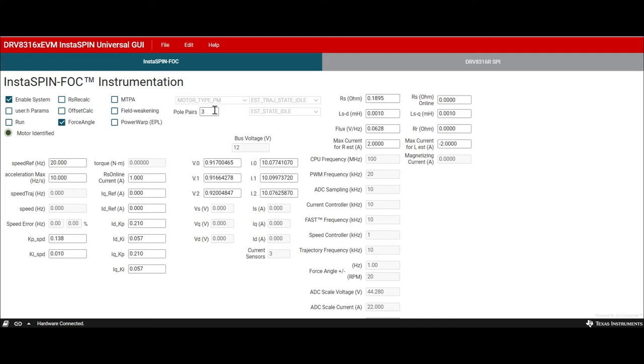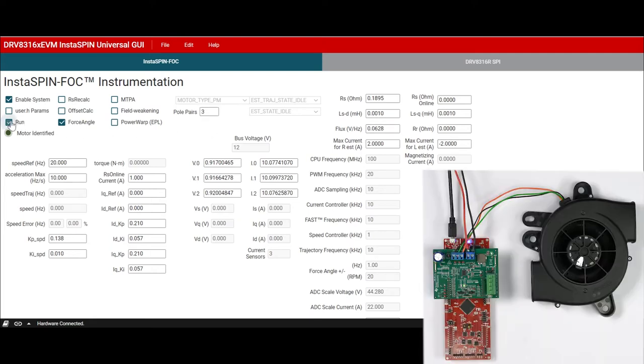Next, configure the number of pole pairs in the motor and press Enter. Another parameter is the estimation current for motor resistance and inductance. This should be set to about 10 to 20% of the maximum motor current. Once configured, click on the Run button.